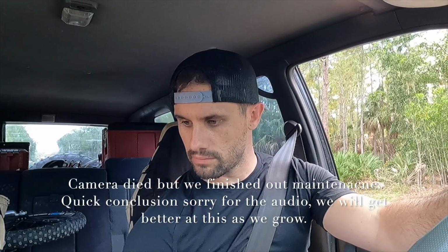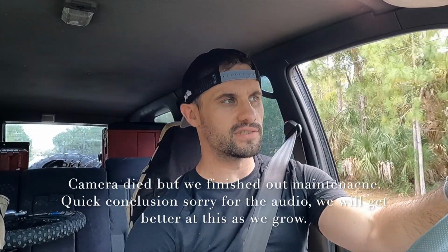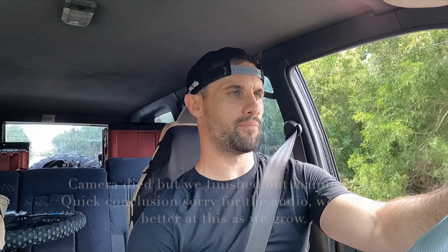All right, so we have wrapped up today's job. Two-system maintenance. Master bedroom had a problem. My initial assessment on the problem was that it sounded like there was probably a clogged drain line. I videoed and recorded the main maintenance for the big system, all the steps I like to take, excluding the electric heat test, which had already been done by the home inspection beforehand. So I didn't feel the need to kick it on now, but they just wanted to make sure the system was clean and operated properly as far as cooling went.